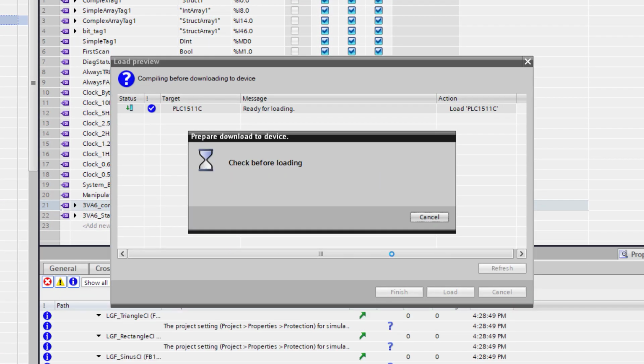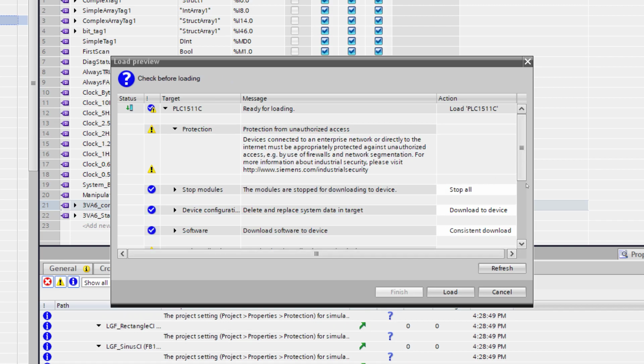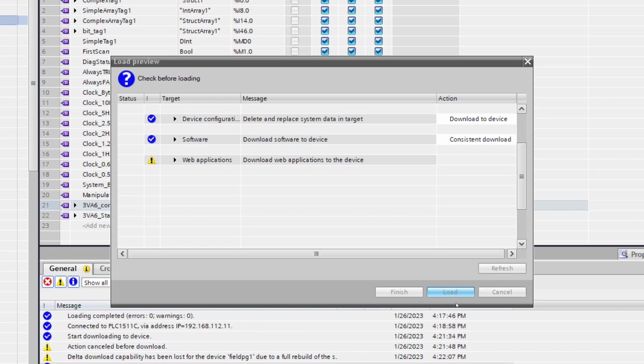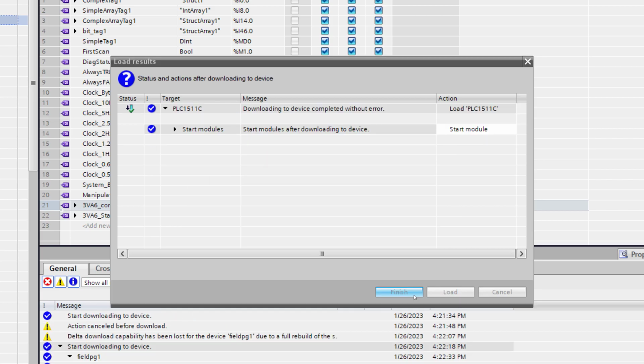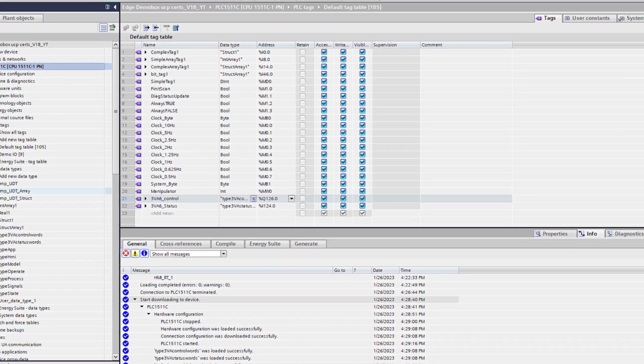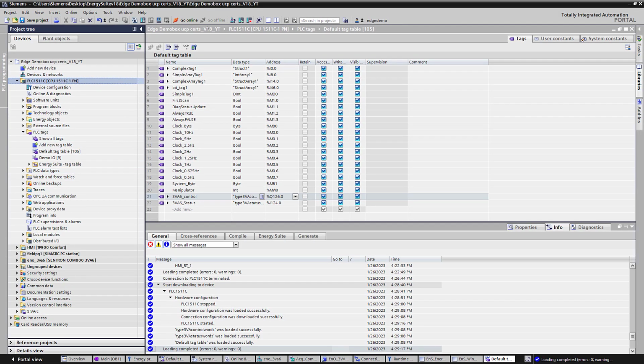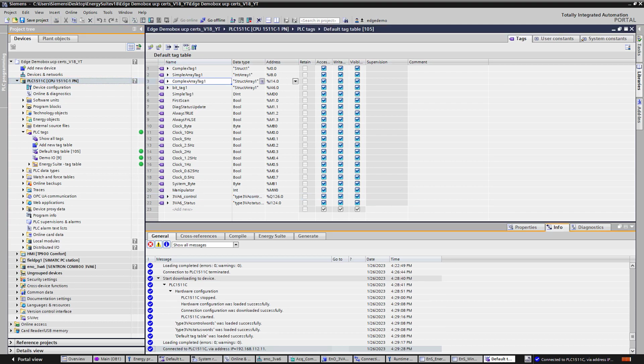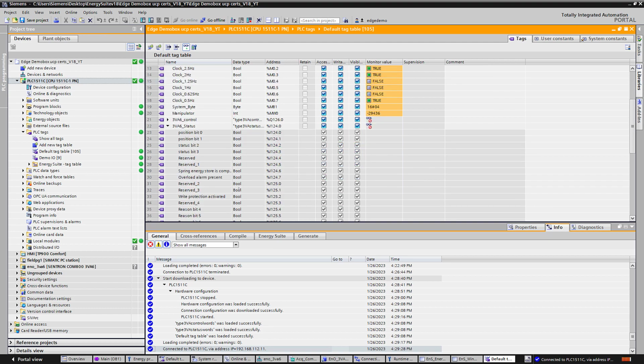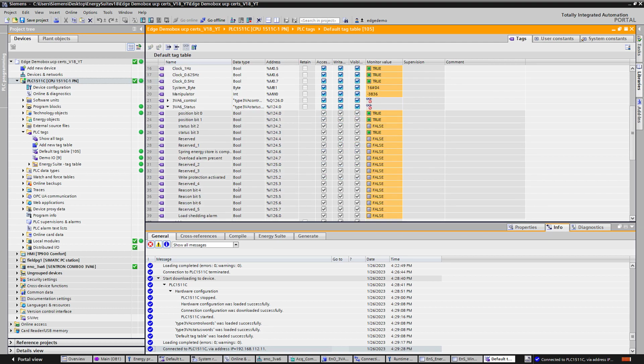We'll go ahead and download this to the PLC. Notice the compilation and then the loading. Finally, we can finish and start the module. And then we'll start by going online with the PLC. And we'll go online to see that. And then we actually have data within the status control word.